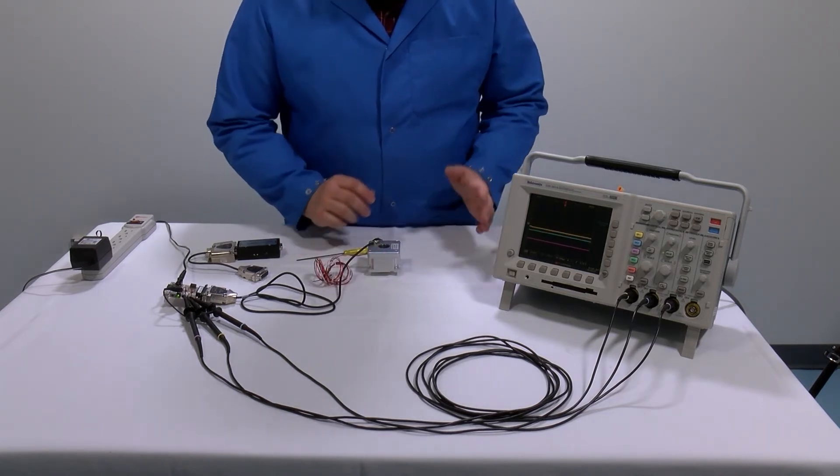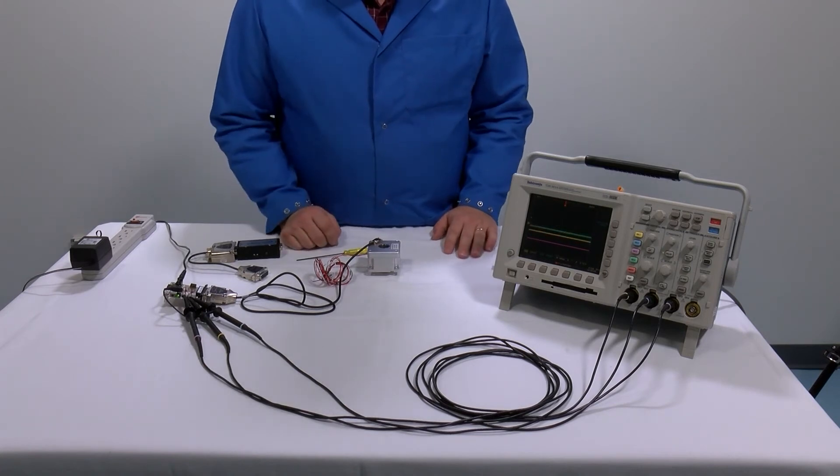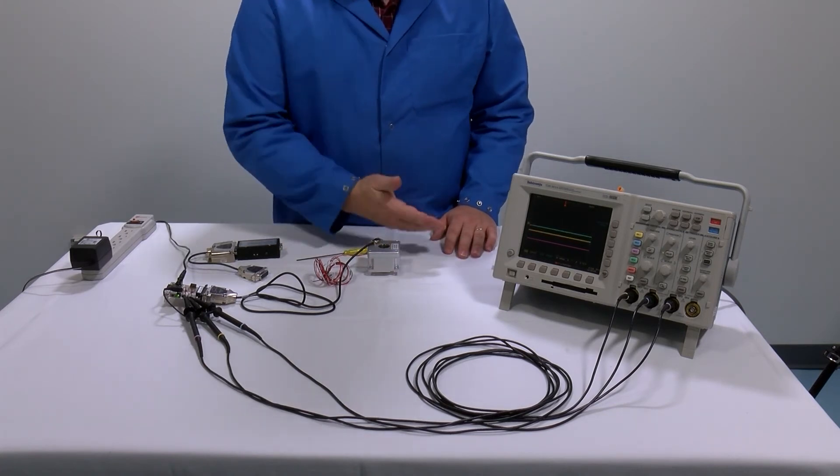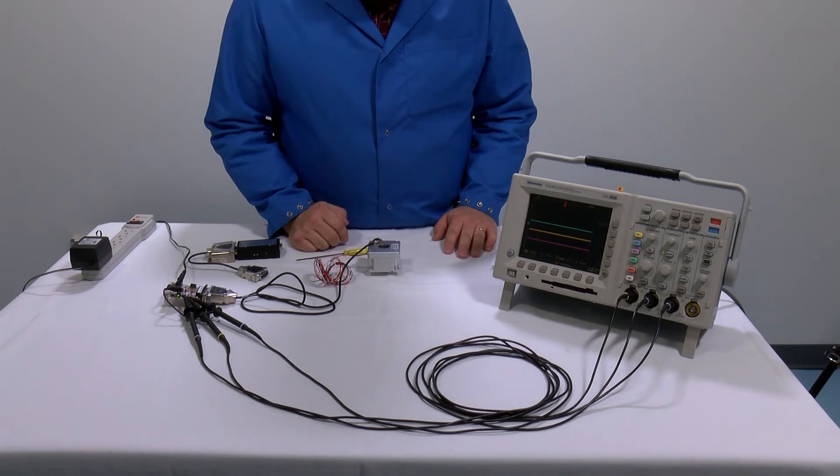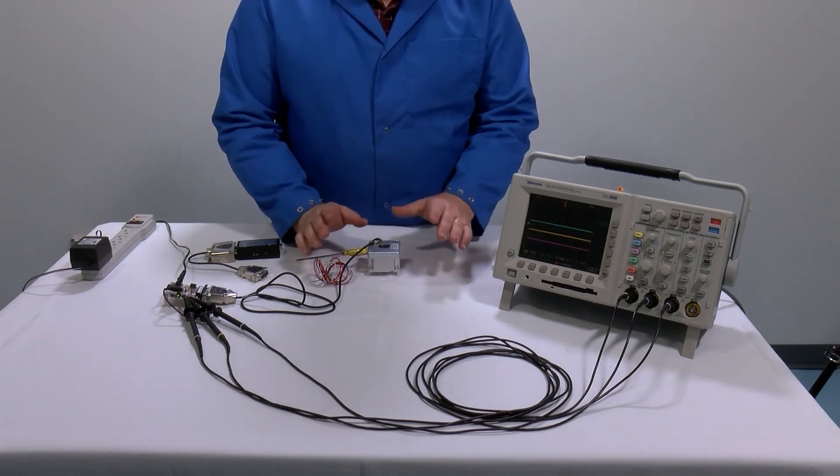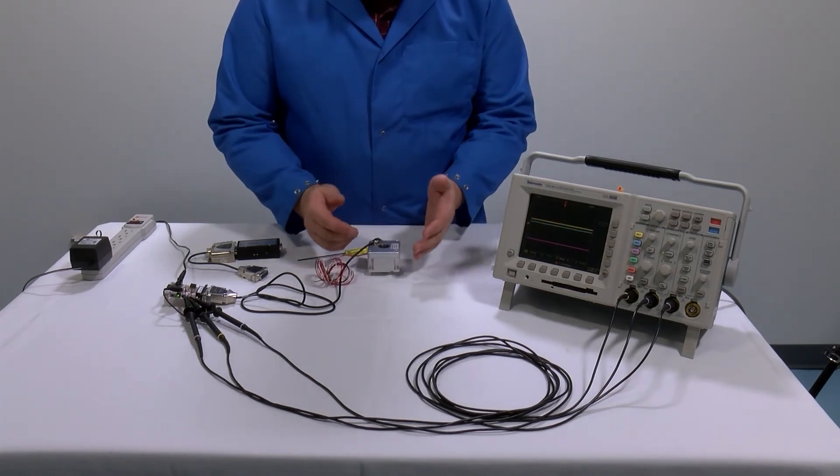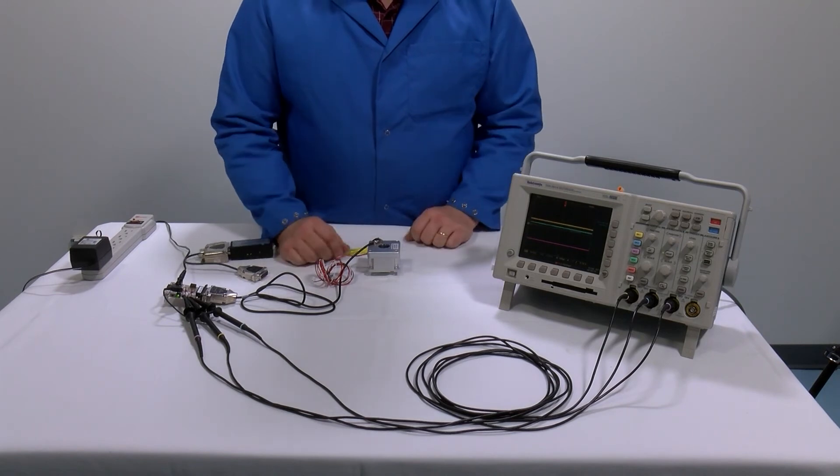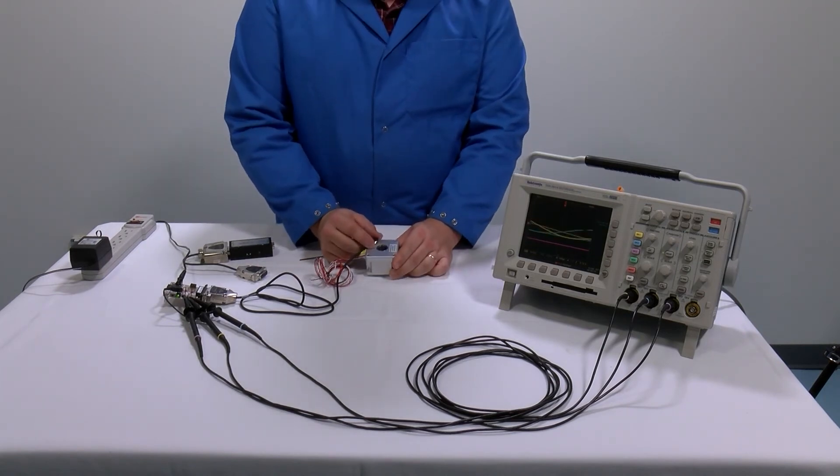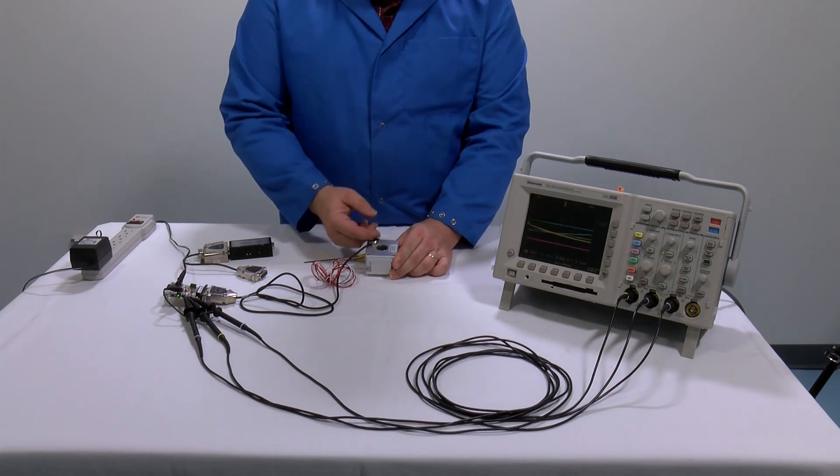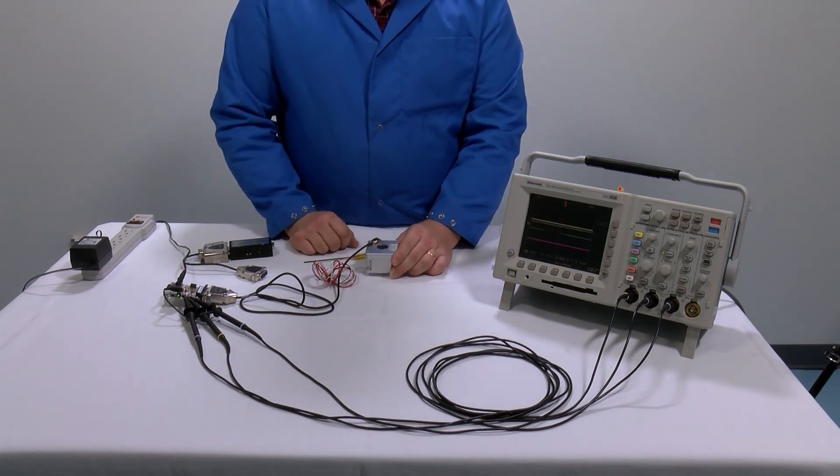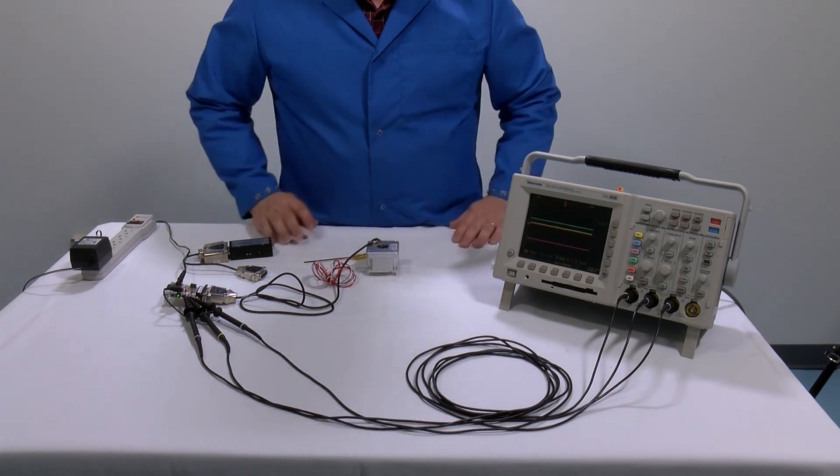Now if in the event you cannot get to at least 800 millivolts peak to peak and an index window trigger, that means there is something wrong with the setup and you'll need to either have the encoder replaced or perhaps you will need to remove the encoder head and check the scale for contamination. All right, thank you.